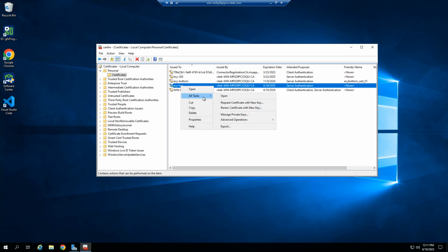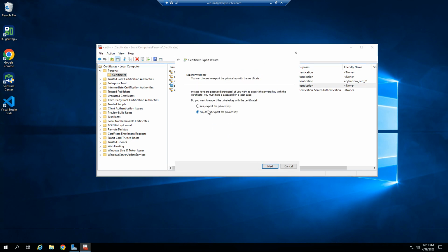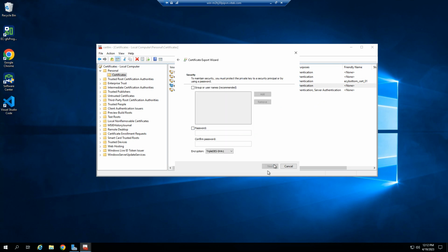Now the last part of this is we want to export this certificate. We do want to export with the private key. This is exactly all we need, and I'm only going to demonstrate an Eclipse controller today, but for a Niagara instance, Niagara doesn't want PFX formatted certificates. It would like to have PEM type certificates.